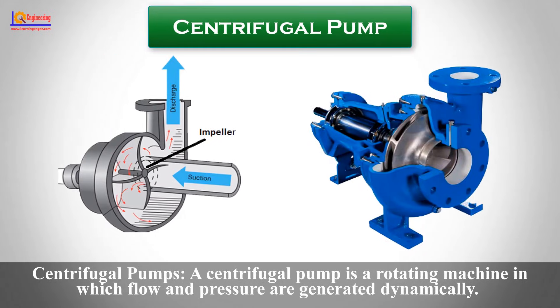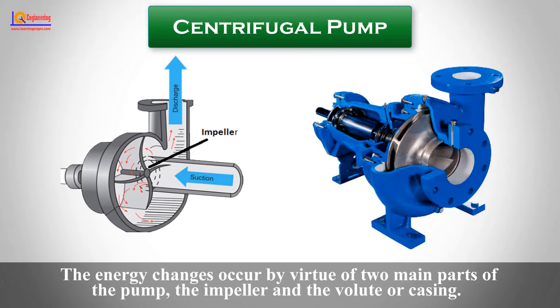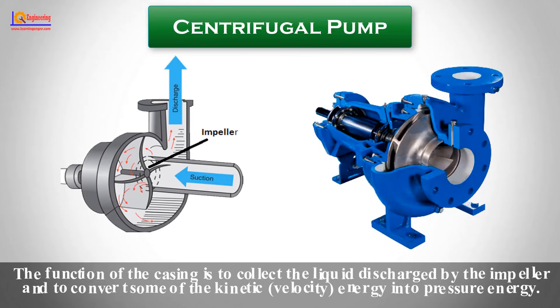A centrifugal pump is a rotating machine in which flow and pressure are generated dynamically. The energy changes occur by virtue of two main parts of the pump: the impeller and the volute or casing. The function of the casing is to collect the liquid discharged by the impeller and to convert some of the kinetic energy into pressure energy.